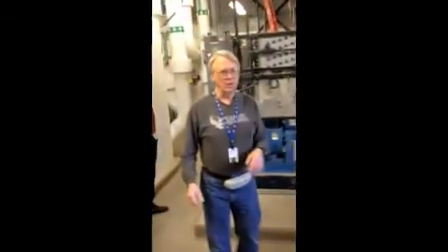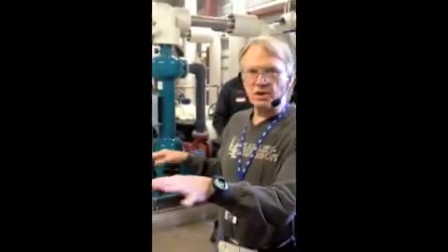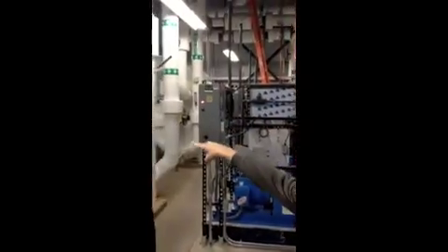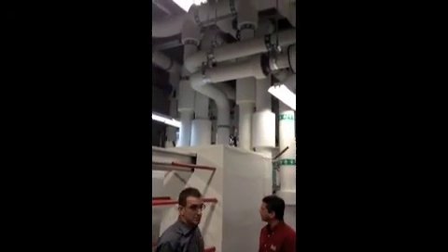Okay, the next thing I'm going to do is take you into the pump room. This is responsible for circulating water to all the expansion directions. On the right-hand side here is the primary loop. This circulates water out through the cooling towers and back, and it goes then through the heat exchangers over here, where it meets the secondary pump loop.